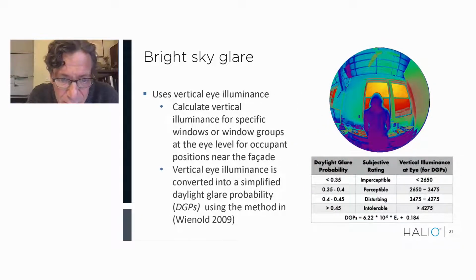For bright sky glare, we're controlling this using a metric of calculated vertical eye illuminance at eye level for occupants near the facade. Once calculated, we convert this value to simplified daylight glare probability. The chart to the right helps explain this a little bit better. So if we measure a vertical eye illuminance at eye level of less than, say, 2,650 lux, the DGP subjective rating is that the glare source is imperceptible. For values greater than 2,650 lux, we would start tinting our glass in steps relative to these DGP settings. Or if we were controlling shades, we would just lower them.